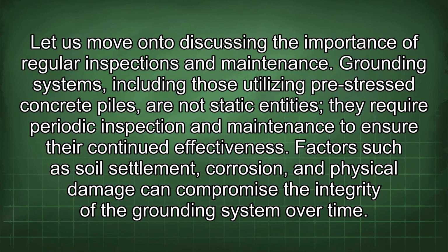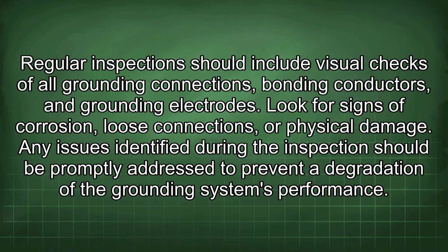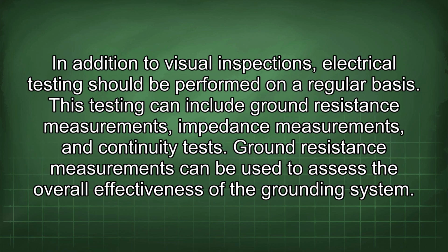Factors such as soil settlement, corrosion, and physical damage can compromise the integrity of the grounding system over time. Regular inspections should include visual checks of all grounding connections, bonding conductors, and grounding electrodes. Look for signs of corrosion, loose connections, or physical damage. Any issues identified during the inspection should be promptly addressed to prevent a degradation of the grounding system's performance. In addition to visual inspections, electrical testing should be performed on a regular basis. This testing can include ground resistance measurements, impedance measurements, and continuity tests.